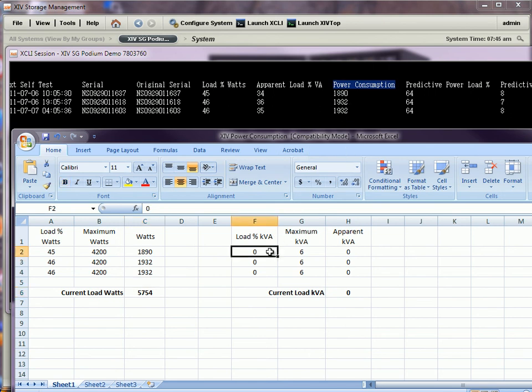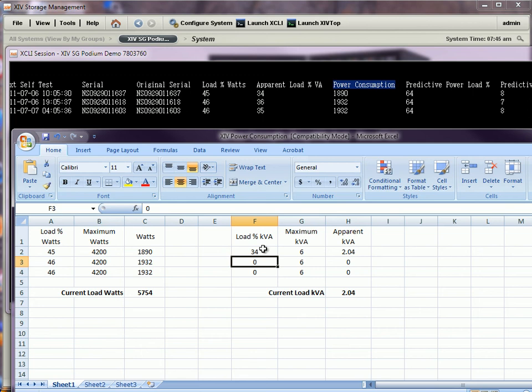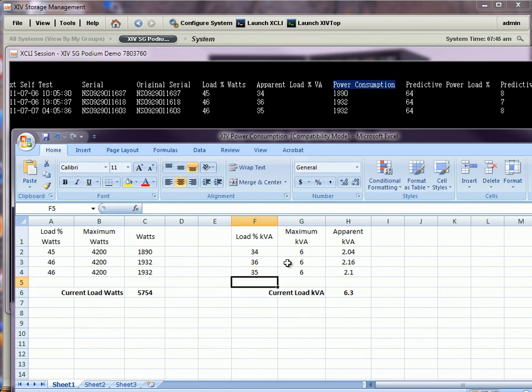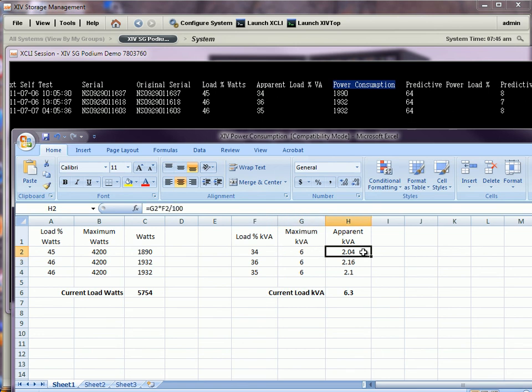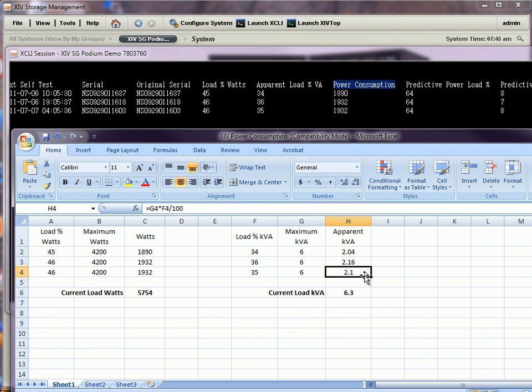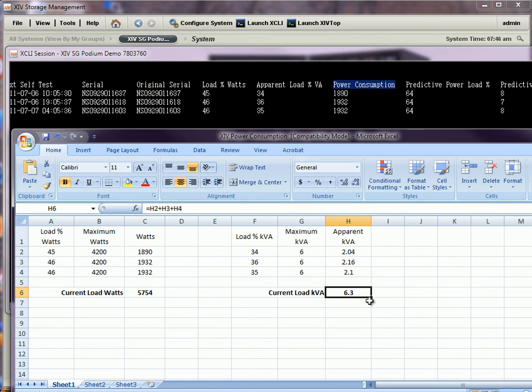With the load KVA percentage, it's a very similar thing. 34%, 36%, and 35%. I know the maximum KVA is 6. So, to calculate the apparent KVA, I simply combine the two numbers as for that formula there. I do that for all three UPSs, and then I sum them together. So, right now, I know the current load watts, and I know the current load KVA for my XIV.